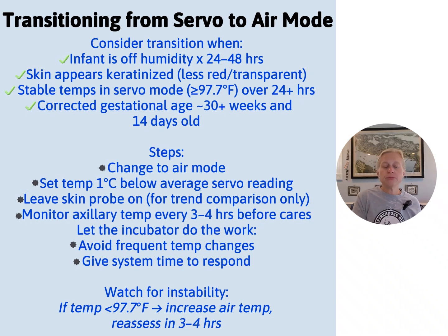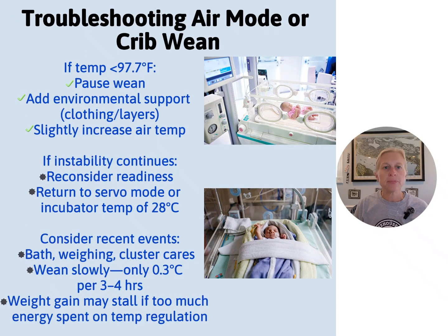Again, we don't want to have frequent temperature changes, but really this is quite helpful and quite warm for these infants, especially if they have a sleeper on underneath. So getting them in here, tucking them in well. I think when you've got this going on and the baby's really tucked in here, it's tricky to be on servo mode. So if I'm here, I'm switching to air mode, even if I leave the probe on for a period of time to monitor and watch for that temp instability.